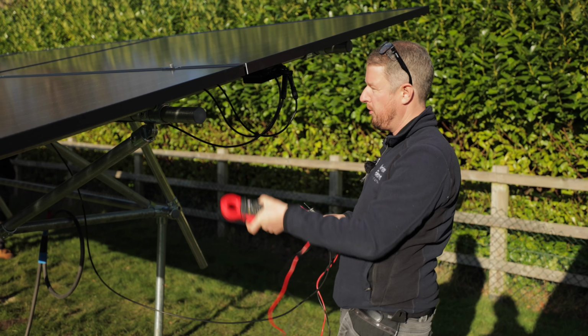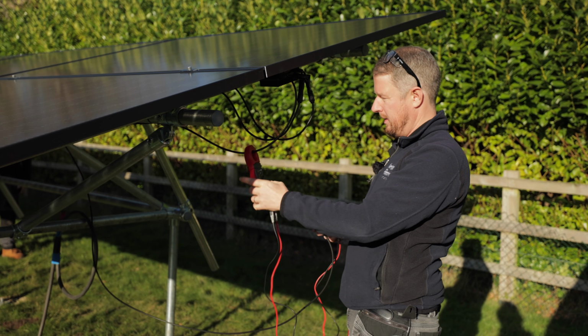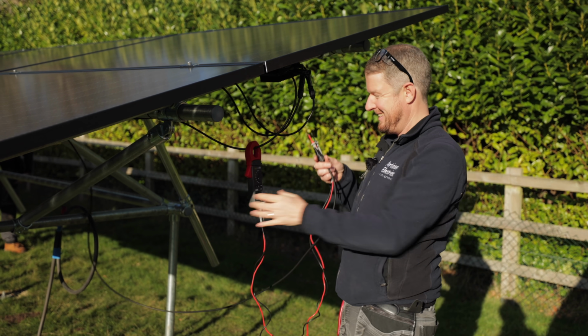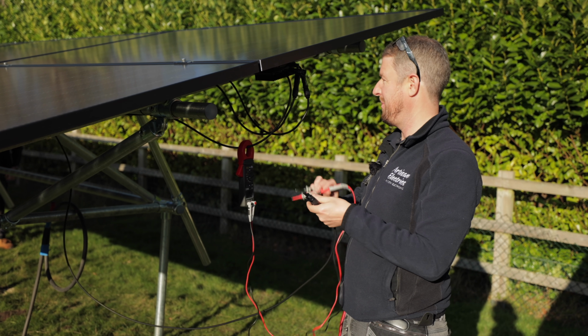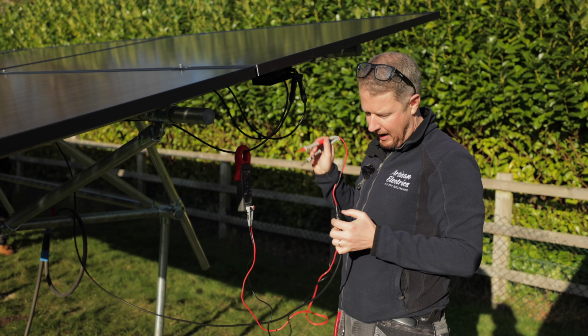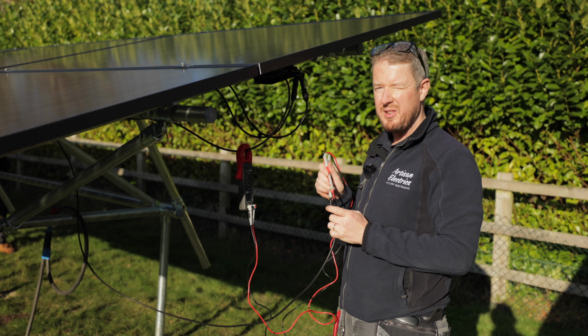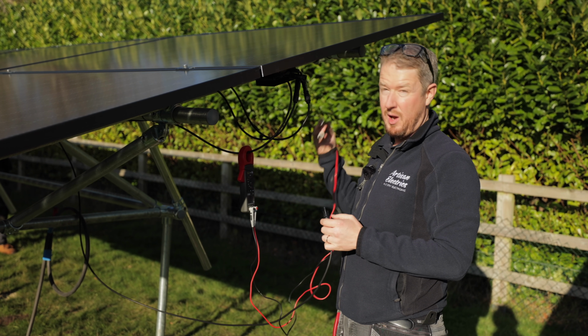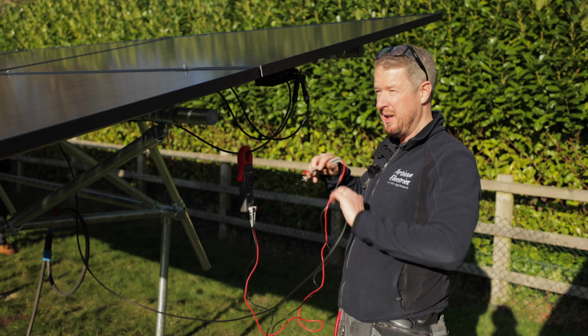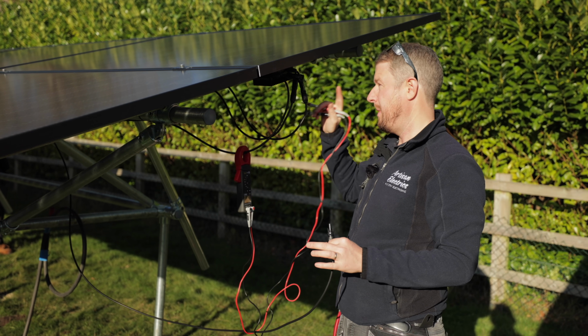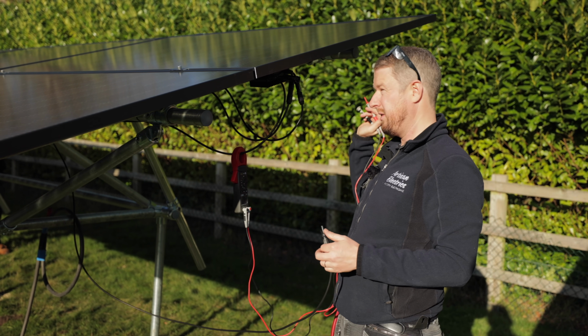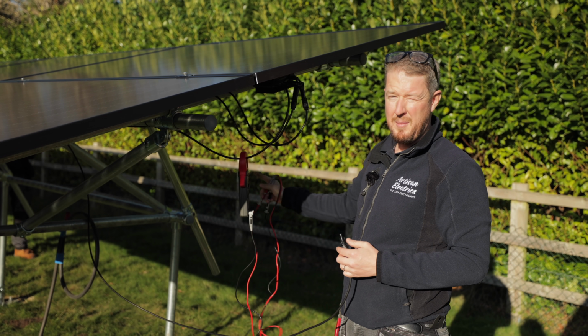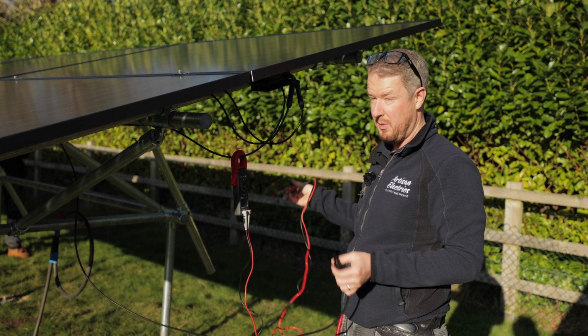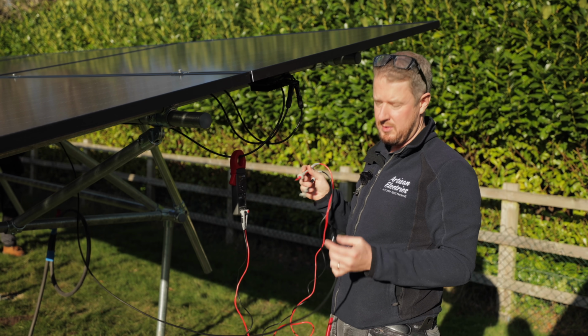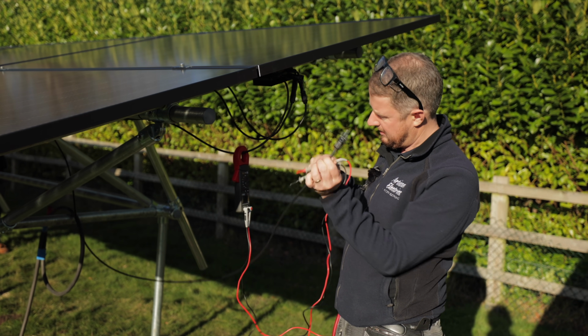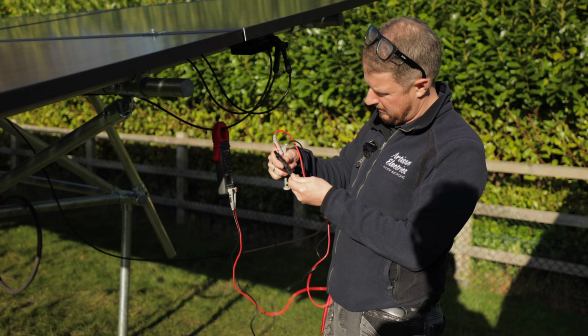This is one of those moment of truth moments where you test to see whether everything's been wired up properly. So we're going to do a polarity test on each string. We're looking for 1 volt per optimizer, because with the SolarEdge system, since it's an optimized system, you don't get the full string voltage, but each optimizer gives out 1 volt. We've got 30 panels per string, so that means 15 optimizers, so we should have 15 volts per string. We'll use our DC voltage multimeter here.